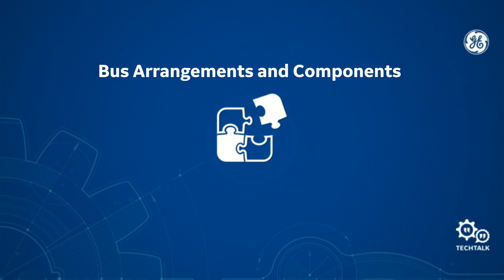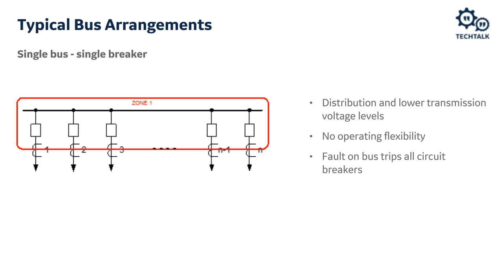Bus arrangements and components: One of the simpler bus arrangements is the single bus or single breaker arrangement, found mostly at distribution and lower voltage levels. It offers no flexibility in terms of operation — if you need to take a bus outage, you must take all breakers associated with that bus out of service, removing all sources and loads. Similarly, if there is a fault on the bus, all breakers must be tripped.